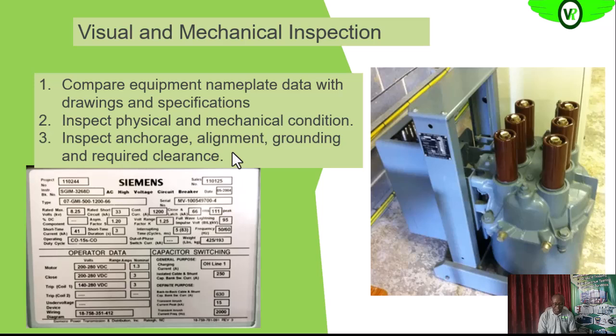Then we want to look at the anchorage to see that it is firm enough to carry the weight of the circuit breaker, and that during operations they will not play. We want to also check the alignment and check the grounding connection, that they are firm. If there are specified clearances and tolerances within the circuit breaker by the manufacturer, we want to be sure that such tolerances and clearances are met.